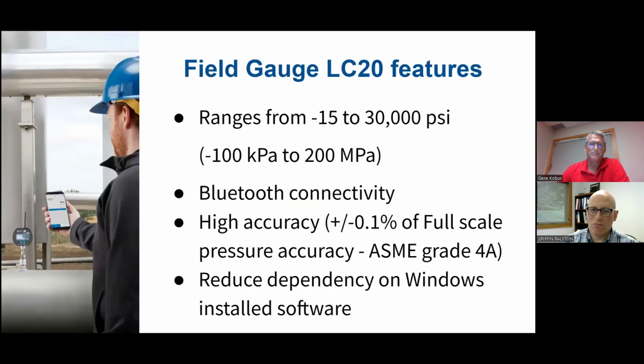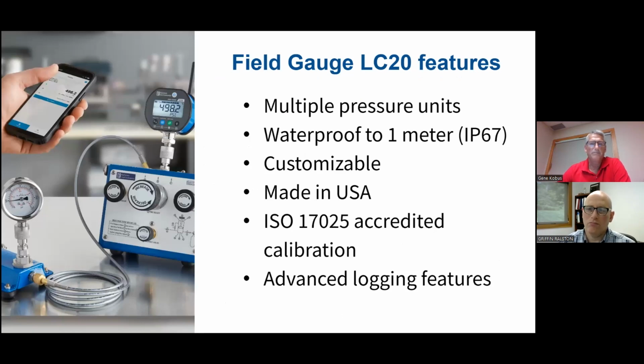Let's take a look at some of its features. There are 15 pressure ranges available from -15 to 30,000 PSI. Most ranges, 500 PSI and below, are calibrated for vacuum as well. It's equipped with Bluetooth 5.0 technology, enabling seamless connectivity with smartphones and tablets. Its accuracy is plus or minus 0.1% of full scale. And the Field Lab mobile app reduces dependency on Windows installed software, which is a big benefit in highly regulated industries. It can display pressure readings in a variety of units, including PSI, bar, kPa, and MPa. It's waterproof to 1 meter. It can be customized by removing engineering units and adding custom units and adjusting settings.